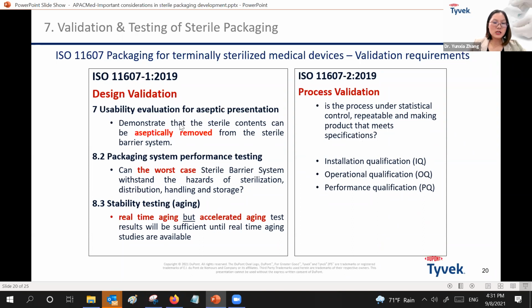For the design validation, it includes usability evaluation for aseptic presentation, which will demonstrate that the sterile contents can be aseptically removed from the sterile barrier system. Also, packaging system performance testing should prove whether the worst case sterile barrier system can withstand the hazards of sterilization, distribution, handling, and storage. For stability testing, there is real-time aging and also accelerated aging. It is to prove that the packaging can stay intact and functional over time. Normally, accelerated aging data will be sufficient for product commercialization, but real-time aging should be started in parallel before the product commercialization.